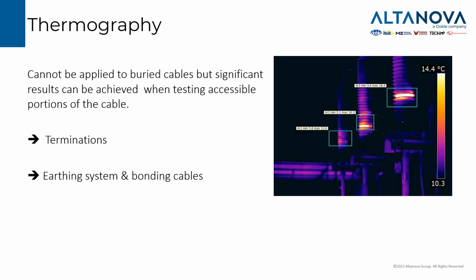As I told you before, it cannot be applied to the buried portion of the underground cable, but we actually have a good percentage of faults in the termination side of the cables. Those are exposed to weather conditions and pollution as well. So we can have an assessment on the terminations, as well as on the earthing system and bonding cables. We can see overcurrent flowing in the sheaths thanks to thermography of the termination boxes and the earthing points of the terminations. So it is a quick test that is normally performed in substations and can be applied as well to underground cable components.